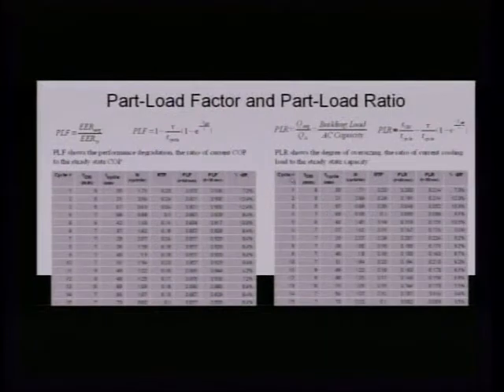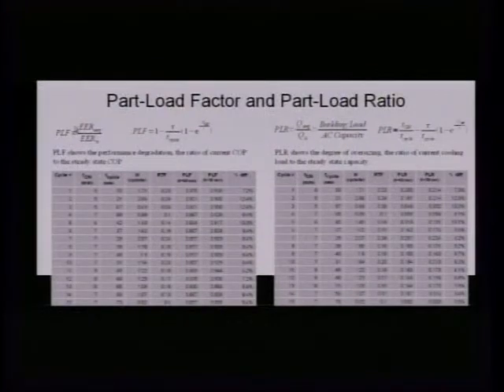So based on these equations, we calculated the part load factor and the part load ratio. Part load ratio, PLR, is basically the building load compared to the air conditioning capacity. So the higher the PLR, the better it is. It means that your air conditioning unit is sized properly for the maximum building load. The part load factor, PLF, is an indication of how your air conditioning unit degrades. The efficiency of the air conditioning unit is EER or COP, so how much worse your COP becomes when it operates under part load condition.